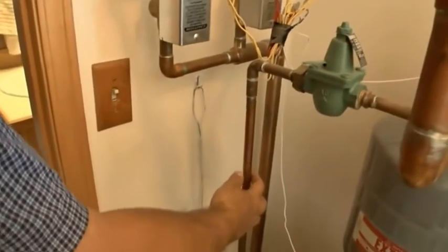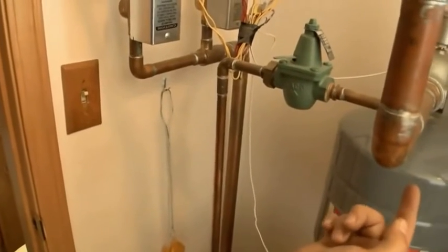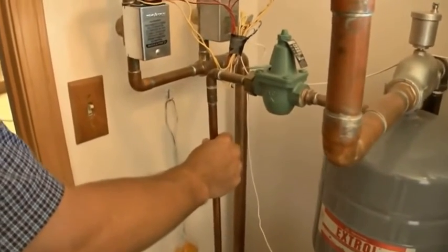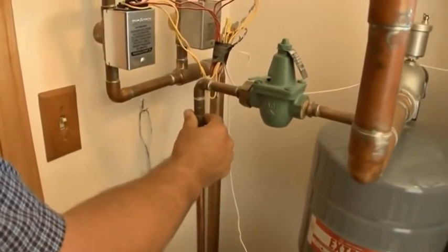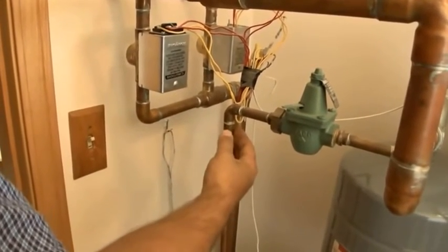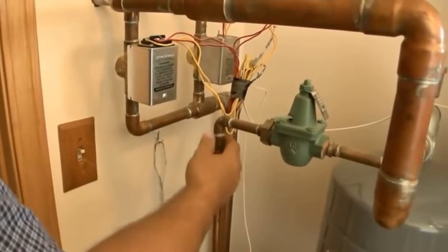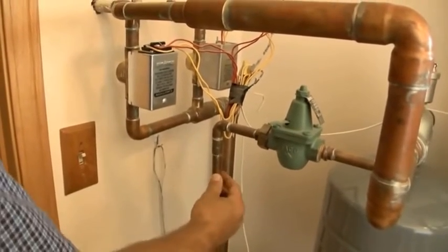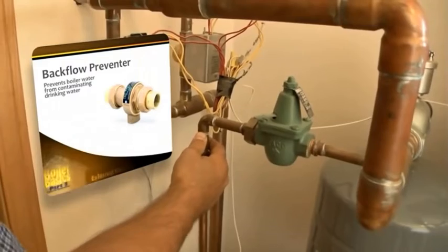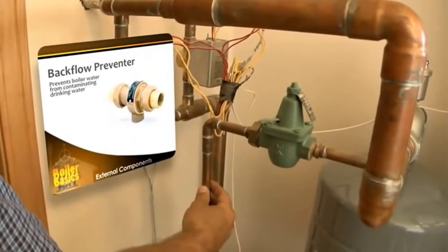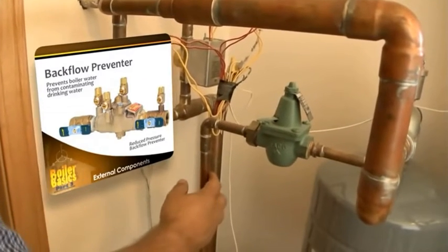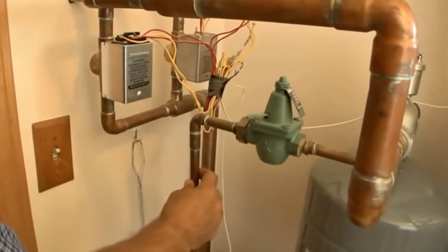One thing that this doesn't have is a backflow preventer. That would prevent any water from potentially going from here into the drinking water of the house. Depending on what your codes are, where you're located. In this particular case, this homeowner is on a well. And when you're on a well, you don't have to have in this area as stringent of a backflow prevention. At the minimum, this would take a Watts 9D backflow preventer. A lot of places would require a reduced pressure backflow preventer. But it really should have a backflow preventer of some sort.